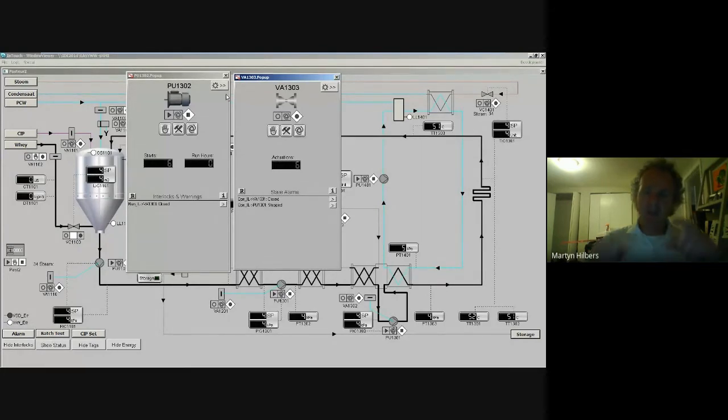So in this case, in a PLC-Easy, in a Lego brick representation, I've got a valve software module and a pump software module, and I click that pump on top of my valve through those 8 parameters. All this information and these commands are now basically coming from the pump. Now, I just issued a manual command to my valve, and if my pump wants to control my valve, it can't, because it's in manual mode, right? The pump cannot take control of it. So the valve reports that back to the pump, and it says, look, your slave is not ready because it's in manual mode.